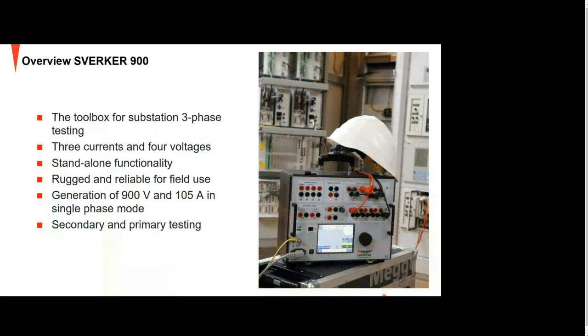So we have a very short overview of the Sverker 900. It's a toolbox for testing substations, and you can generate and test three-phase protection with it. It has 3 currents and 4 voltage generators. And it's a complete standalone unit, which means you don't need to hassle with a PC and have problems communicating in between. It's always the unit itself that you can bring to the substation and do your testing. And it's very rugged and reliable for field use. It's made to be in the field, in the substation.